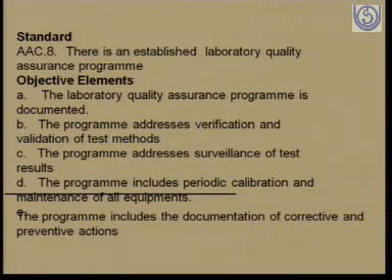And the maintenance of this equipment will result in availability of this equipment throughout to the laboratory, so that there is less downtime and efficiency is maintained. Program includes the documentation of corrective and preventive actions. Whatever variation is there in terms of the results, that can be corrected, and any preventive action in terms of any requirements of equipment can be taken care of in this quality assurance program.